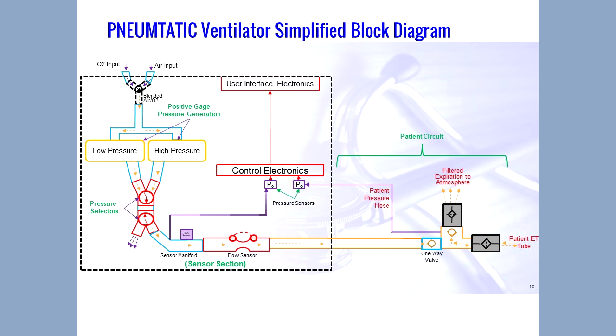They are set by the operator, depending on the state of the patient, and the operator gets instructions from the nurse and sets those two knobs. And then the intent is for the patient to be in that controlled mode for potentially an extended amount of time. The pneumatic system and the compressor system do detect when a patient voluntarily starts breathing and allow the patient assist mode to take over. So this is a very simple schematic block diagram of the pneumatic design.